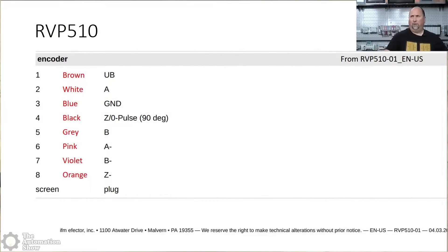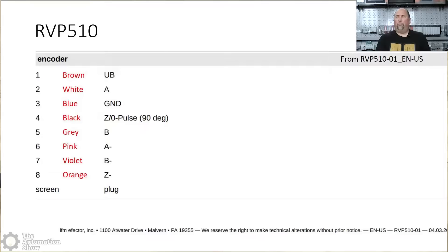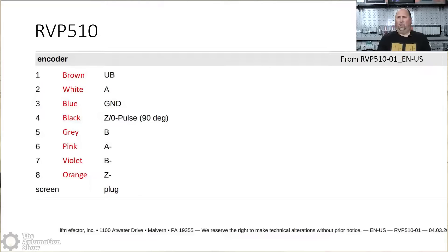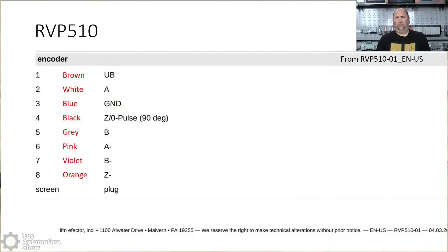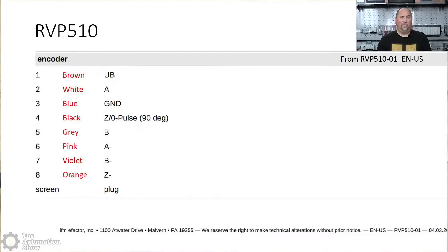So I had to take that information. Then I'll put up a page out of their manual, their RVP 510-01 manual from their website. And you can see I took the color code and I put it right on top of there. So if we look at this, we can see one brown is DC positive. And that's kind of common, right, with sensors.